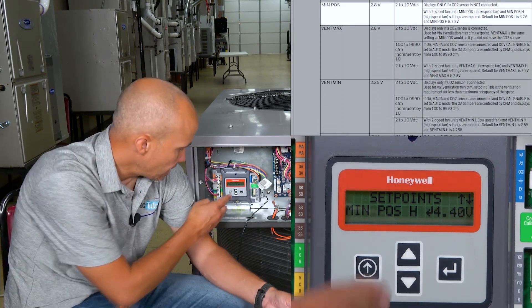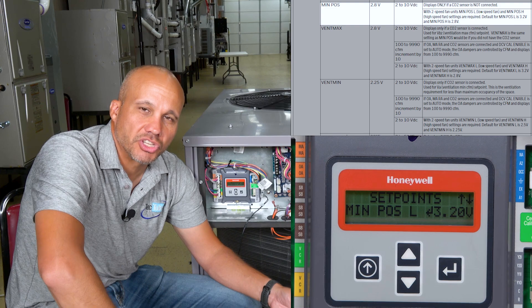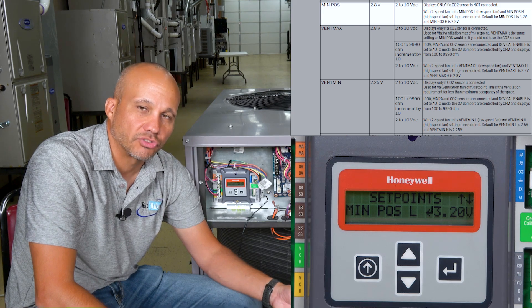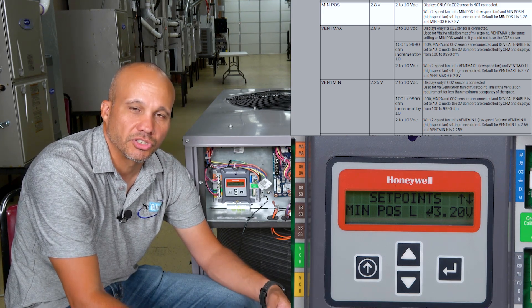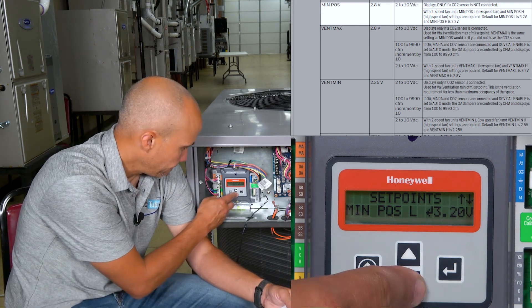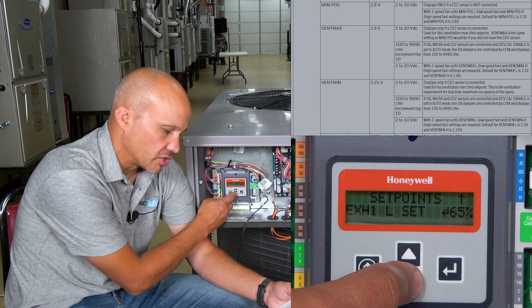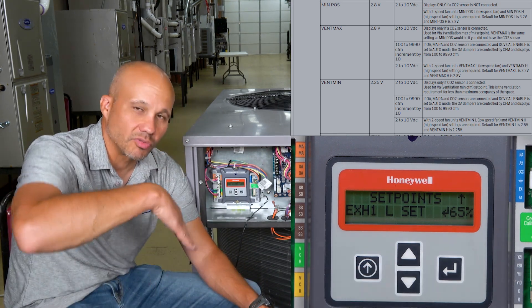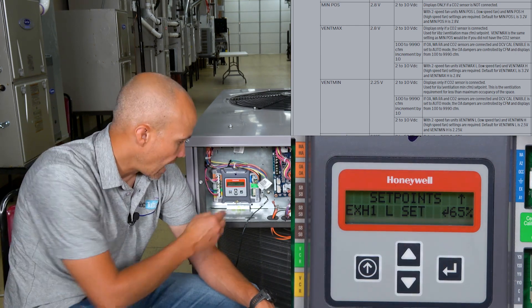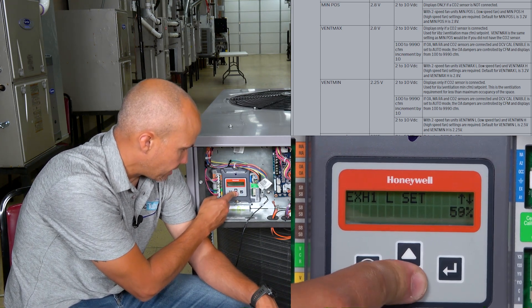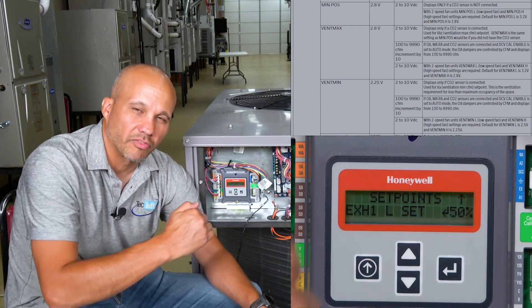Scrolling down, I have Minimum Position H and Minimum Position L — two minimum positions because I told it I have a two-speed fan. If I only had a one-speed fan, there'd be only one. So what damper position do you want for minimum code-required ventilation when the fan is on low, and what do you want when it's on high? I also have an exhaust fan set up: when the damper gets to a certain percent open, turn the power exhaust on. I'll change that to 50 — so whenever the damper opens halfway, I'll kick the power exhaust fan on to relieve the building pressure problem.